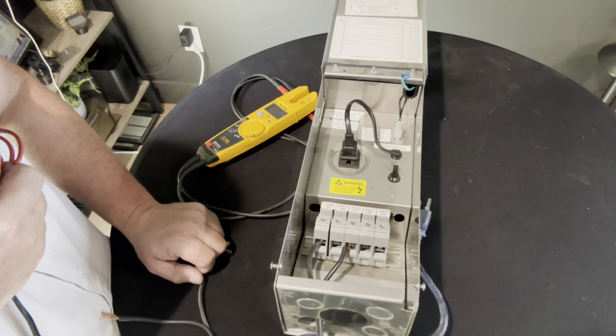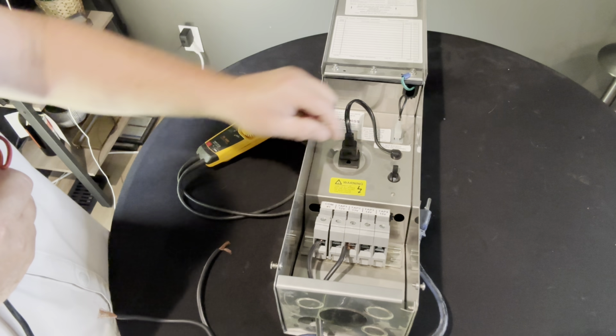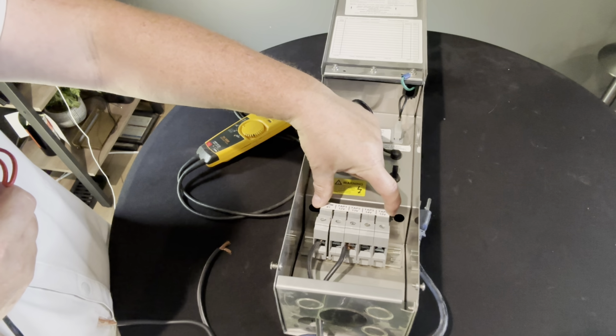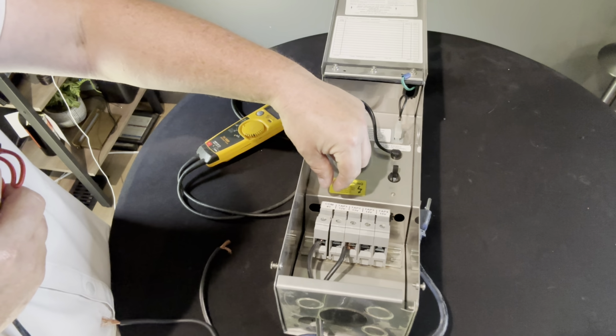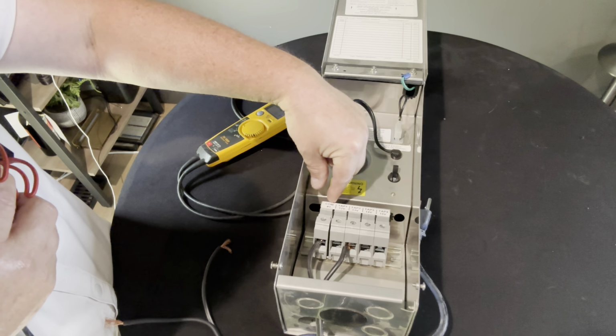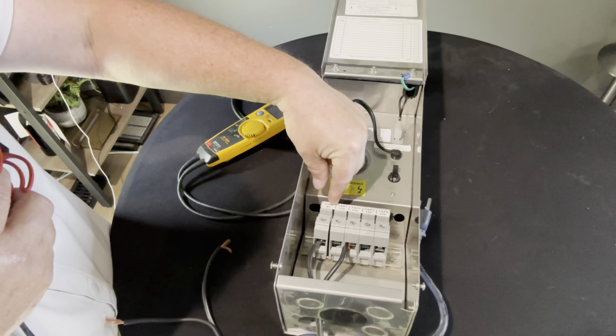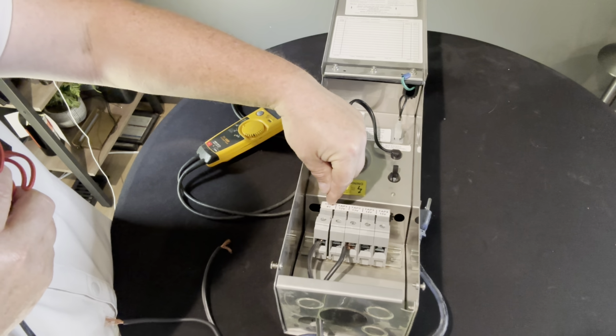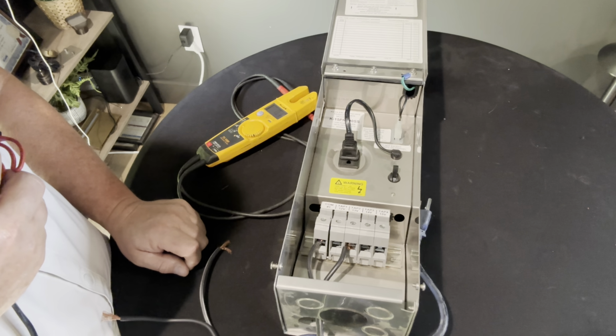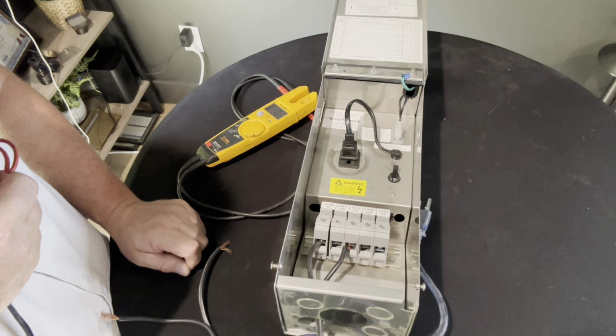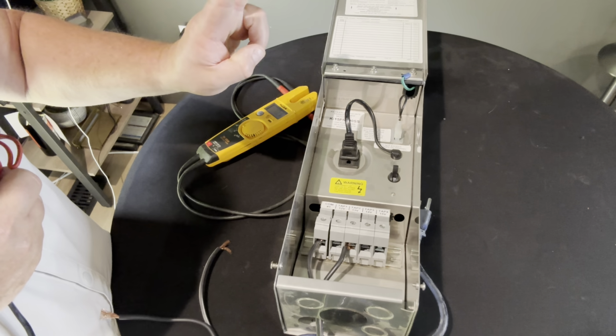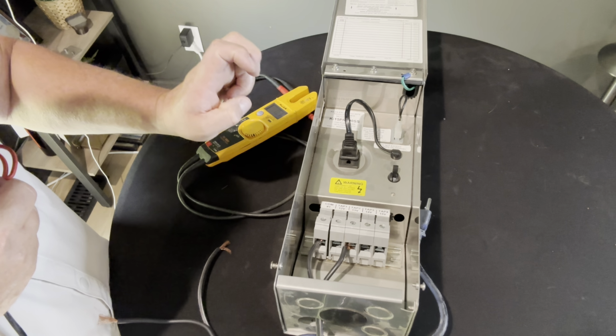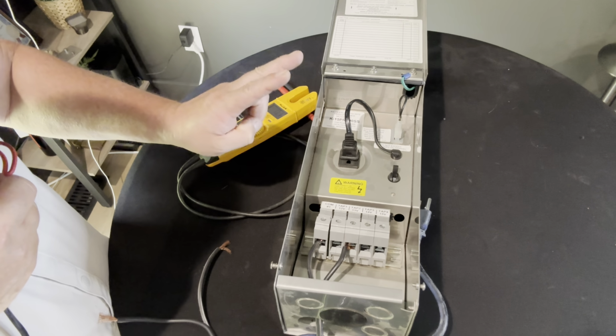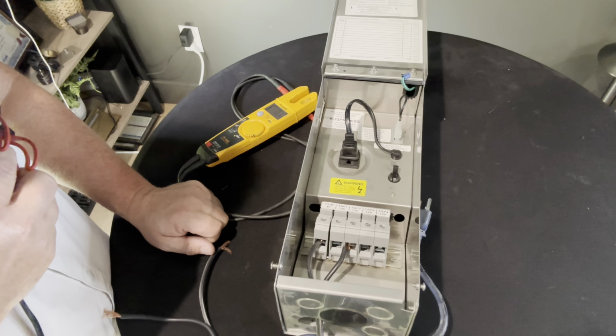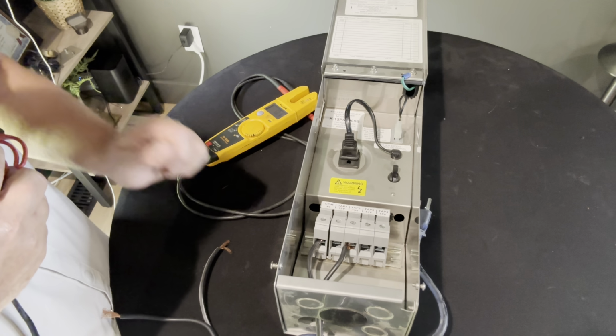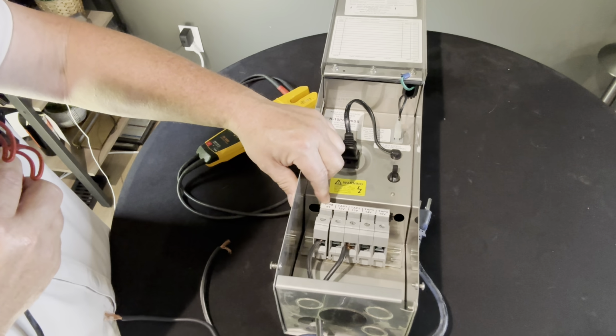Now if you were to buy a 600 watt transformer, you're going to have two of them, two terminal blocks, or two commons labeled COM 1 and COM 2. Each COM is rated for 300 watts, but because we use the 80-20 rule, we only put 80% of what it's rated for.